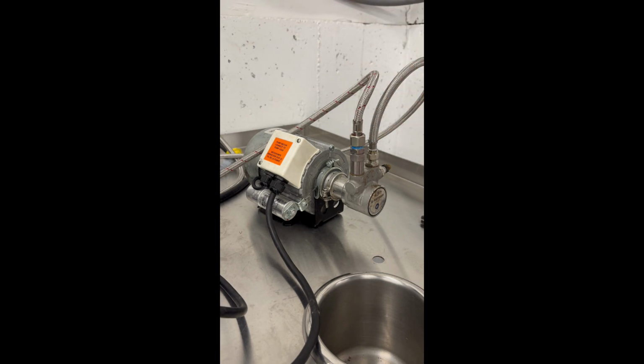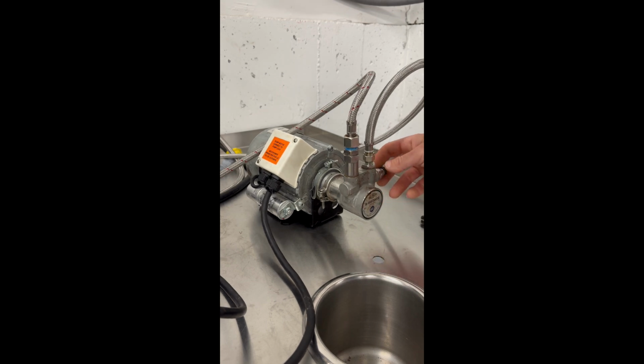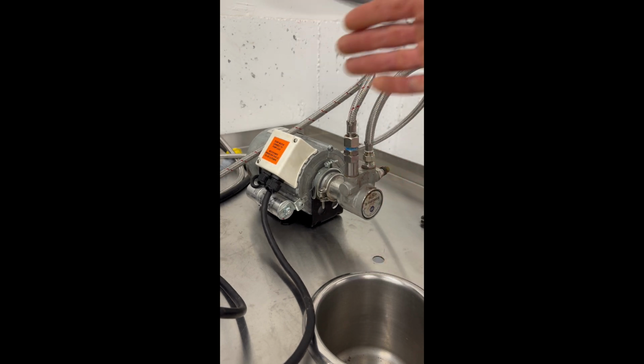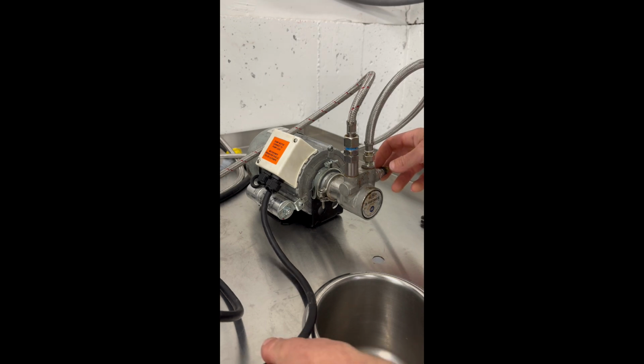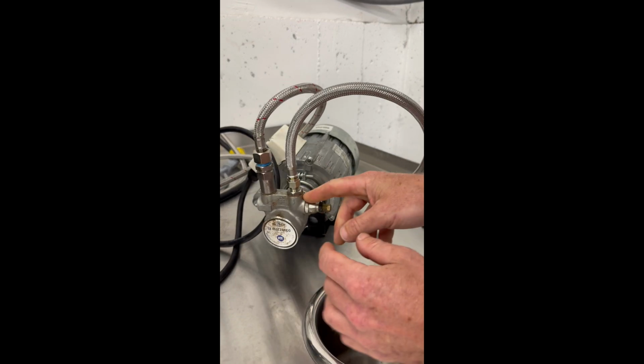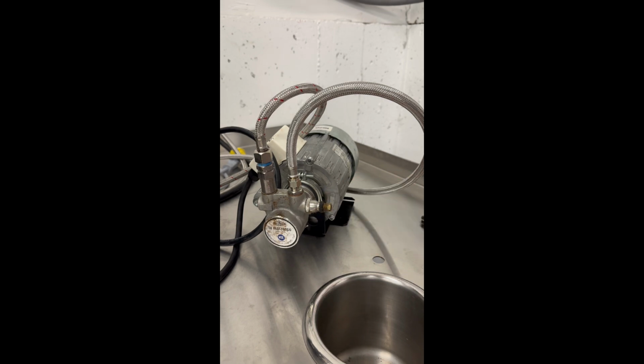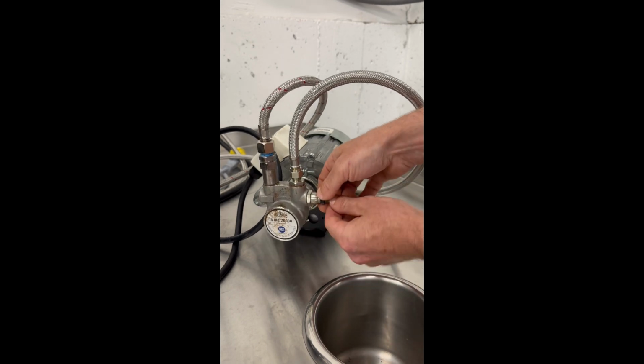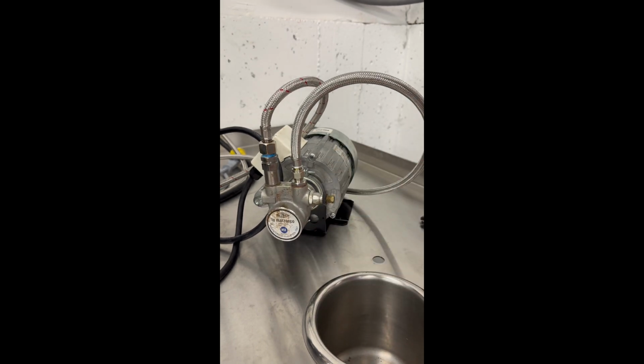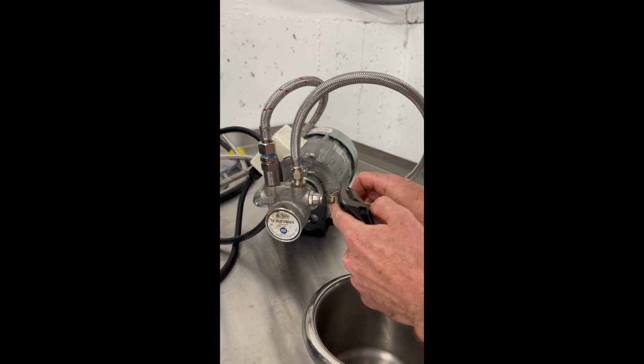Now, if everything's fine and you just need to adjust the pump pressure, say it's like pulling at like 10 bars of pressure or just under 9 bars of pressure, whatever the case may be, where you need to adjust it, this is where you're going to adjust it, right here. So it has this little like locking nut on it, and shouldn't be able to turn it at all. And you're going to need also a wrench, 2 wrenches for this, I like to use. So first, to just unlock it, you want to hold this in place, because this is what you're actually going to be adjusting, this gold piece here.